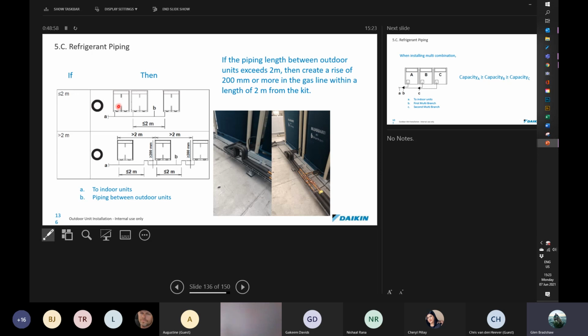The other thing to consider is that sometimes condensers are not evenly spaced or spaced according to the manuals. You'll be quite surprised that in an area where there's free airflow and no obstructions, condensers can actually be placed 25 millimeters apart, which is very close, and that allows for less piping at the condensing end. But when you cannot put them close together, you're going to have to look at using a gas riser, because once this piping extends past 2 meters, you're required to put in a gas riser of 200 up, 200 across, and 200 down.